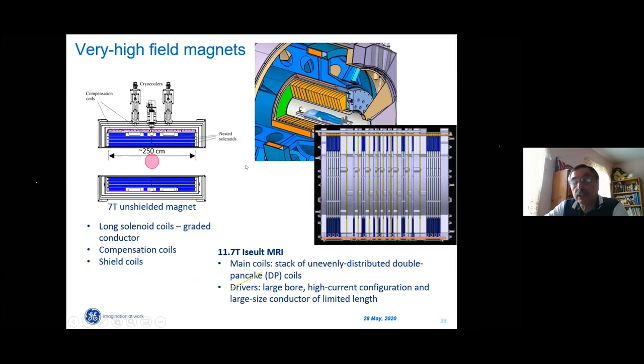Ultra-high field magnets use a different manufacturing technology. Remember that we used multi-coil configuration. This is a 7 Tesla magnet, and they use a long solenoidal design with some coils that compensate the magnetic field. There are additional coils here and here for shaping the field.